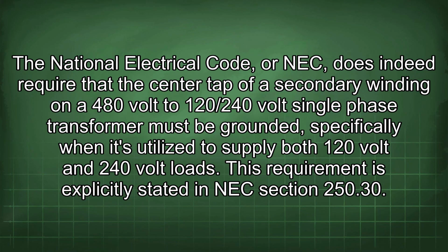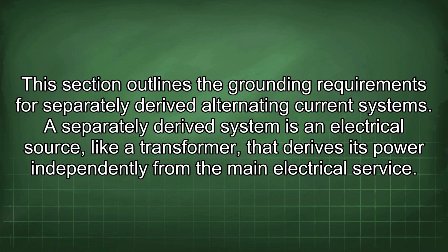The National Electrical Code, or NEC, does indeed require that the center tap of a secondary winding on a 480 volt to 120/240 volt single-phase transformer must be grounded, specifically when it's utilized to supply both 120 volt and 240 volt loads. This requirement is explicitly stated in NEC section 250.30. This section outlines the grounding requirements for separately derived alternating current systems.